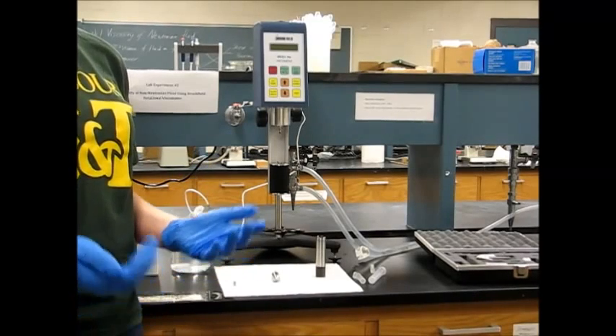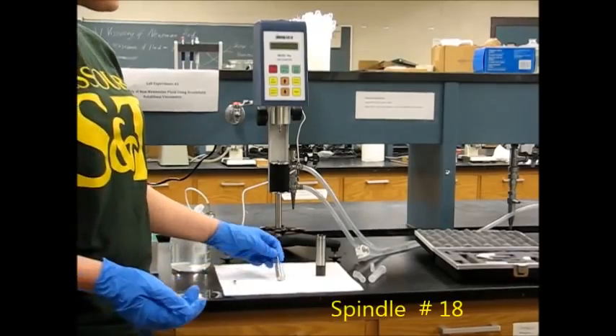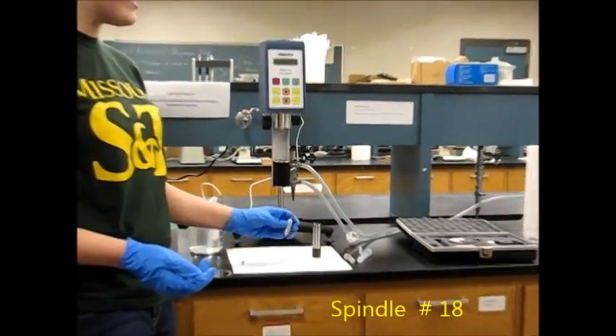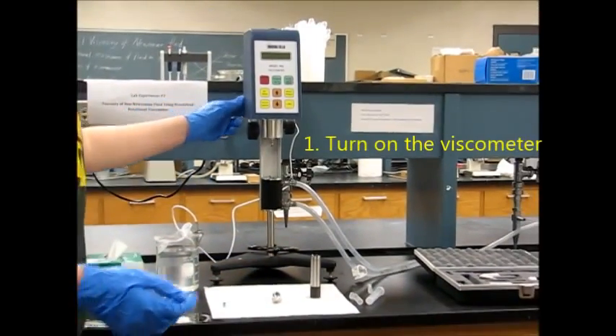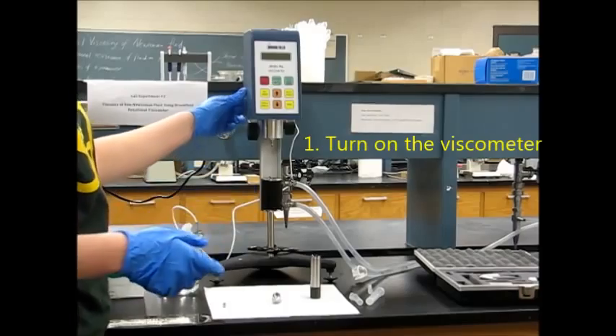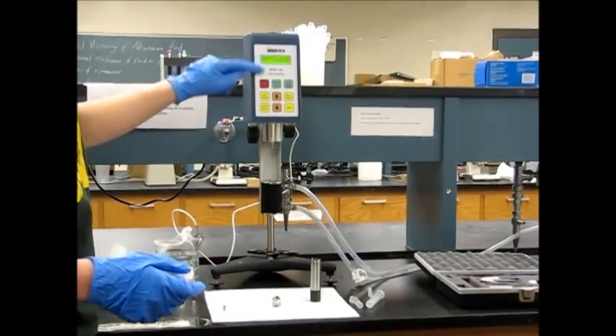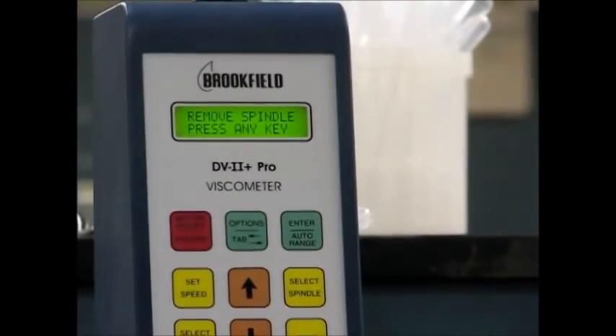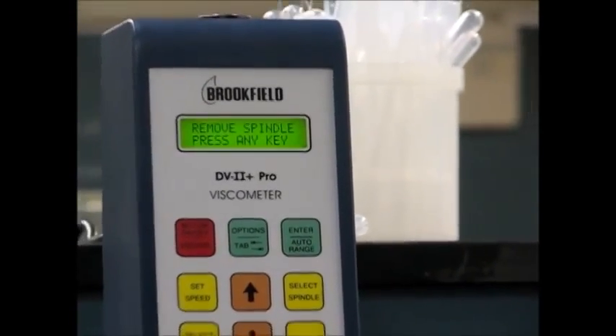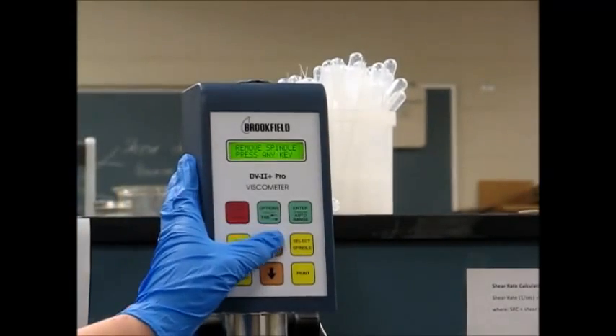For the purposes of this experiment, we're going to use spindle number 18. It has an 18 on its stem. The first thing that we're going to do is turn on the viscometer with the on-off switch on the back of it. We're going to follow the directions on this keypad. It tells us to remove the spindle. We don't have the spindle attached, and then it says press any key.